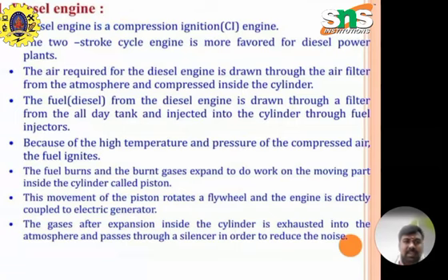So a diesel engine is a compression ignition engine. The two-stroke cycle engine is more favored for diesel power plants. The air required for the diesel engine is drawn through an air filter from the atmosphere and compressed inside the cylinder. The fuel, that means diesel, is drawn through a filter from the all-day tank and injected into the cylinder through a fuel injector.